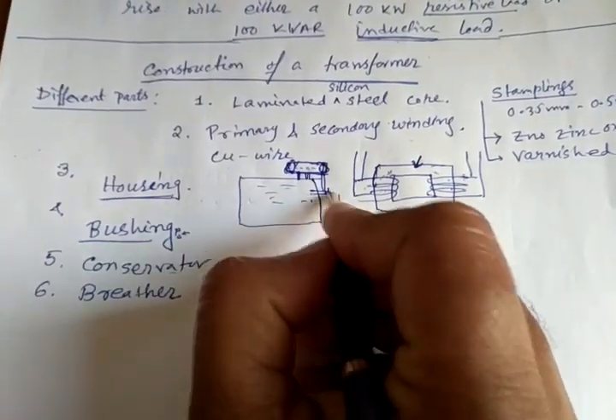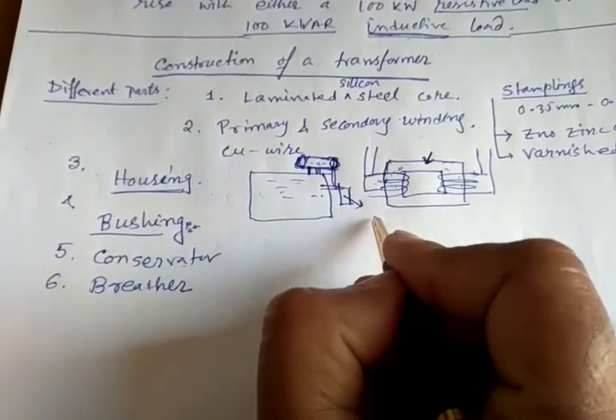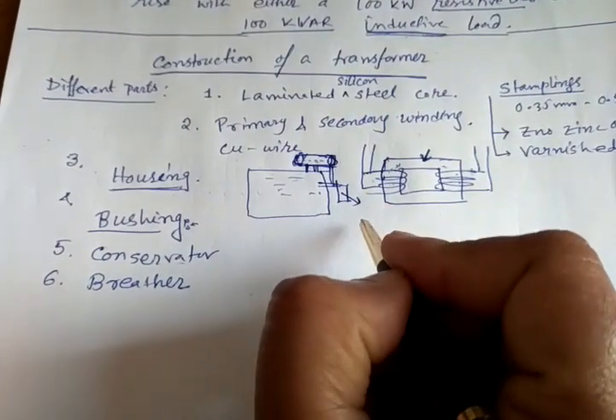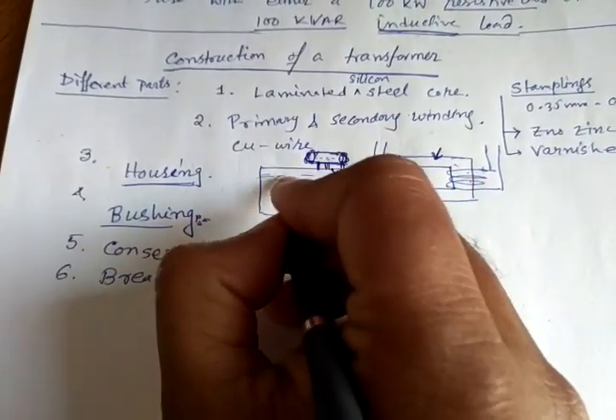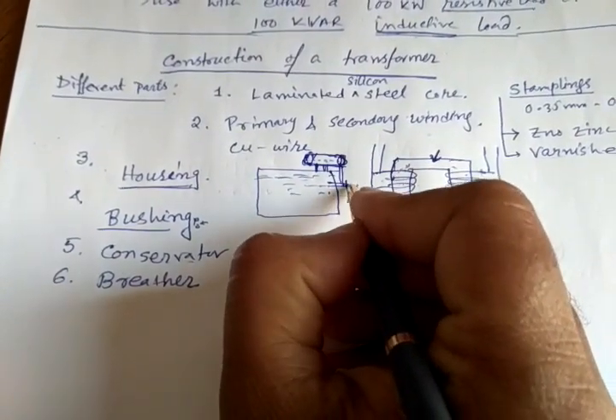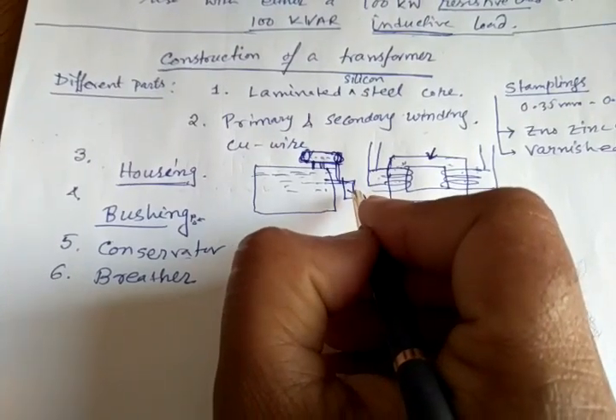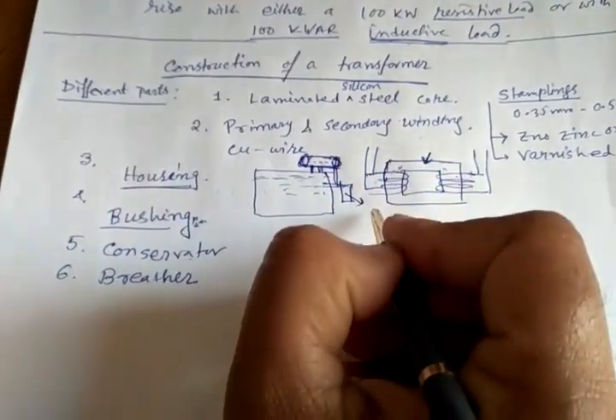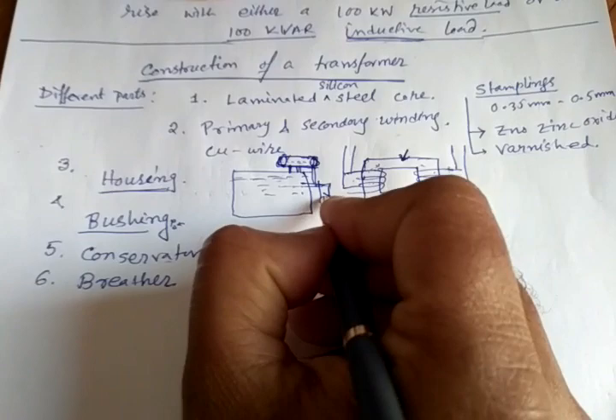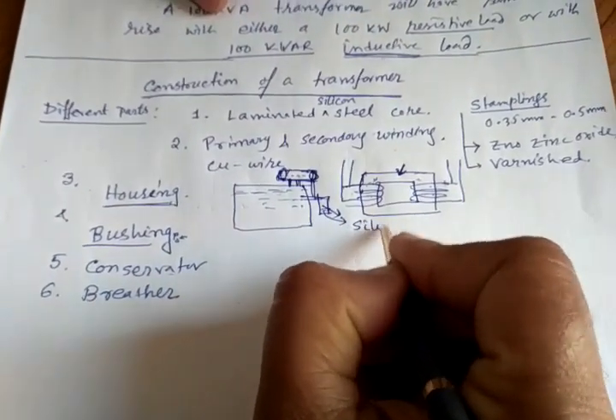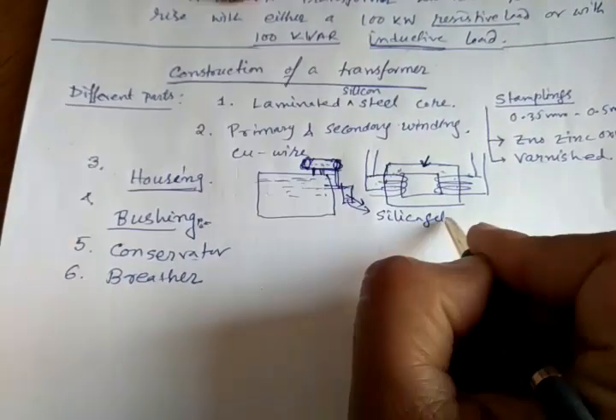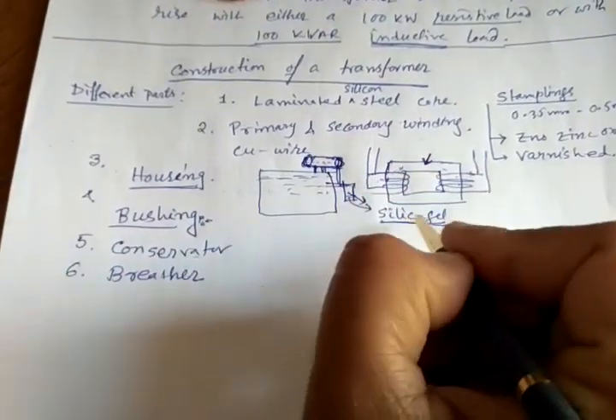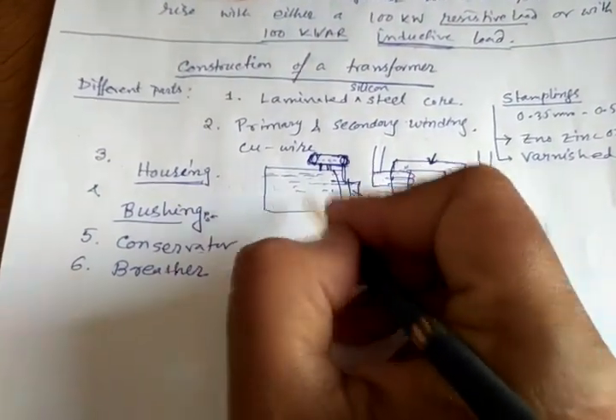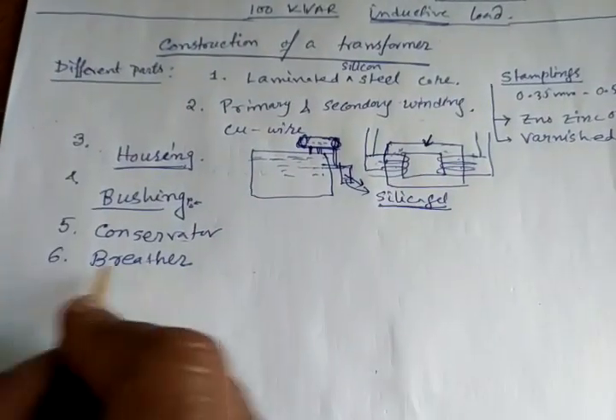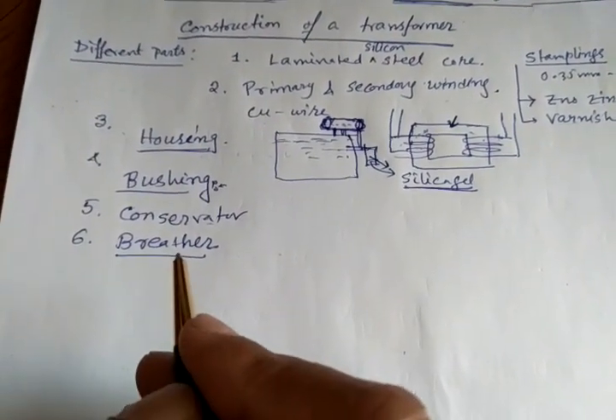It is used for soaking the moisture from the air. Some air is there in the transformers, so that the moisture content in the air doesn't get in or get out, some silica gel is placed. Silica gel actually takes away the moisture content in the air or in the oil. That is known as breather.